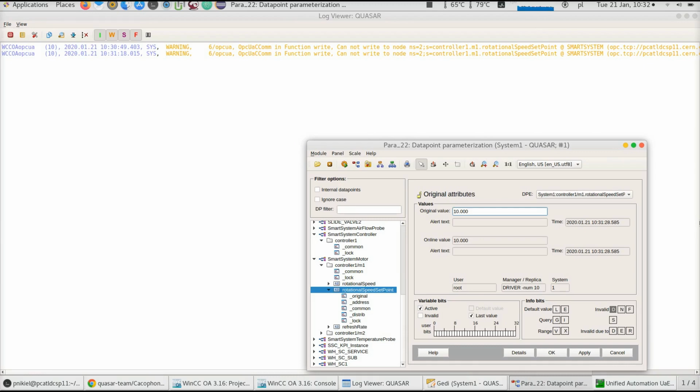It's my private viewpoint, but I have to warn you that you have to double or triple think about what will happen when you are writing things from your control system and you cannot catch if the write was successful, and there's even misleading information, as the value stays wrong.